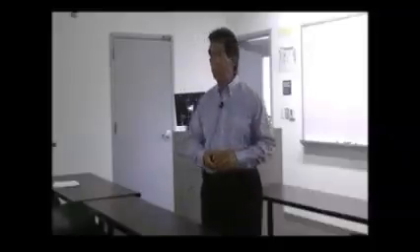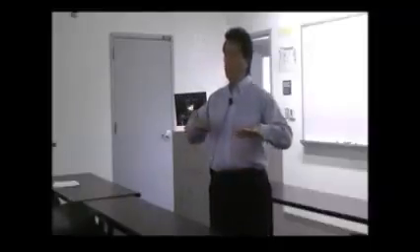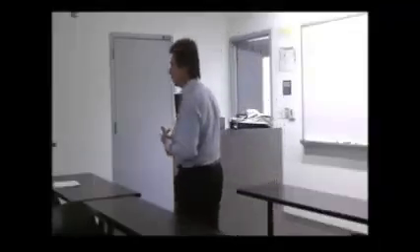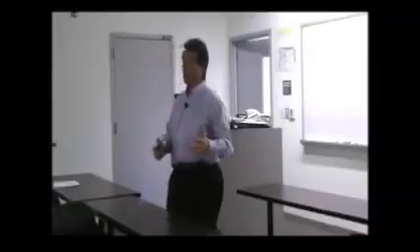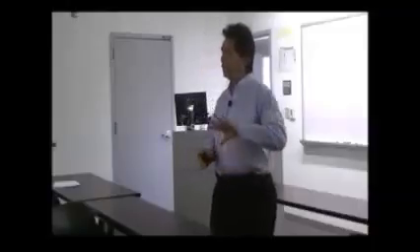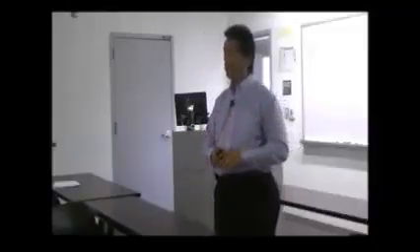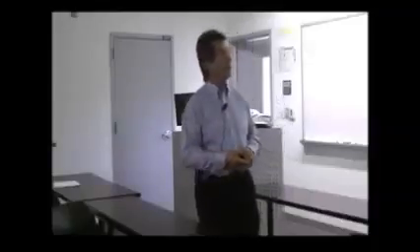So this is the information that we receive back. One would be the infrastructure configuration. Remember I was telling you about the ductwork and how it's configured? Identifying some of the areas where you don't have a lot of air volume, typically at the end of the run. Right out of the air handler, huge volumes. You won't find very much at the bottom of that duct with turning vanes. But you get further back, say 200, 300, 400 feet, the air volume at that point starts to slow down. So whatever's suspended will now start to drop off on that particular one.